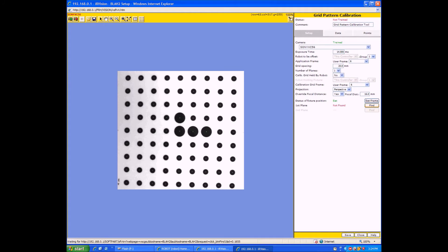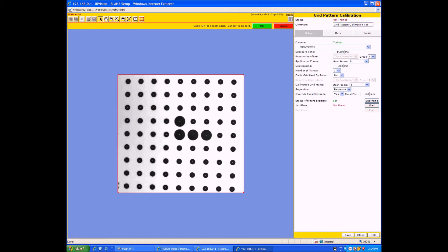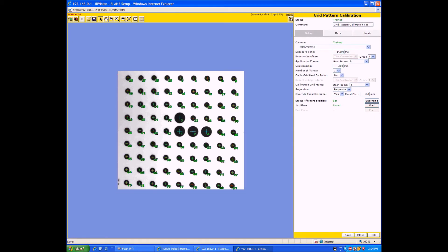Once you hit Find, a box will appear. Make sure the box is covering complete dots — it doesn't matter if it's all the dots, just make sure that they're all complete dots. Then hit OK, and it should put crosshairs over each dot. The large dots will have blue crosshairs and the other dots will have green crosshairs. Make sure your settings are all correct according to the manual, then hit Save and it's done.